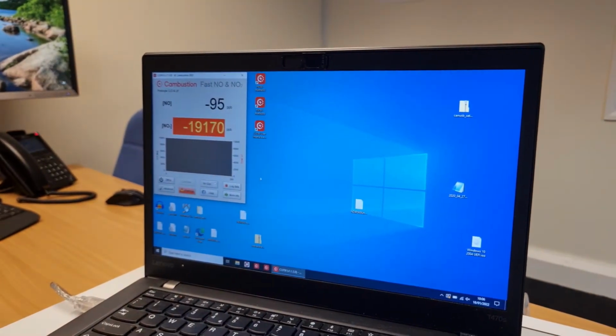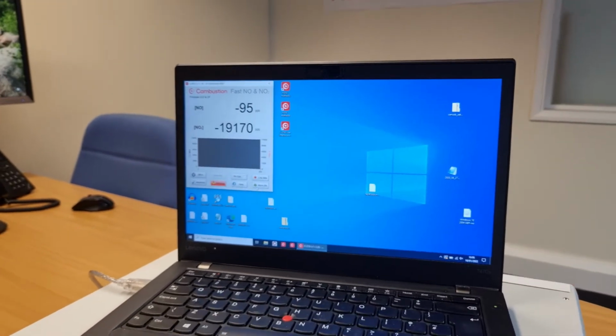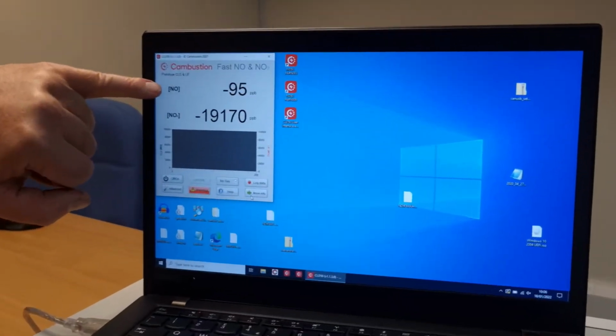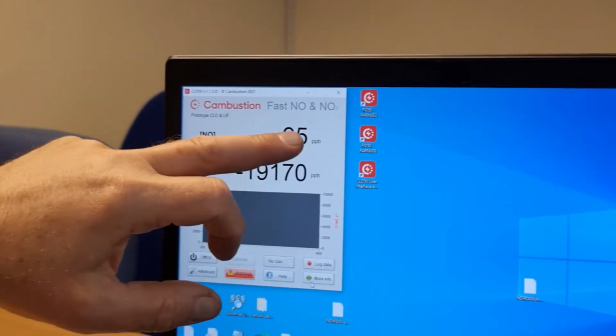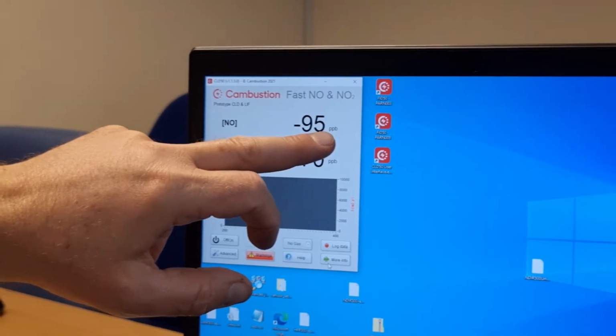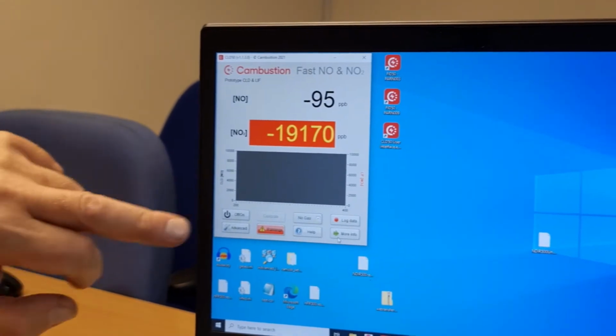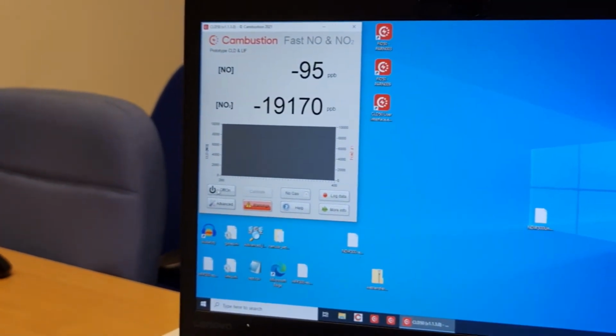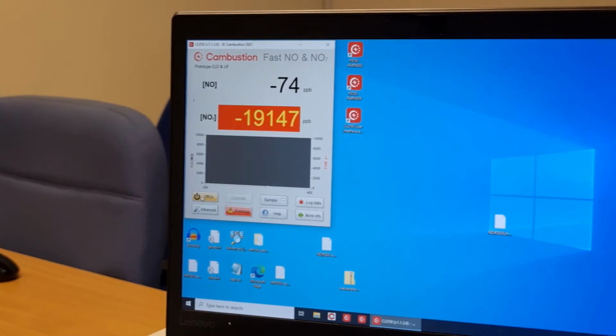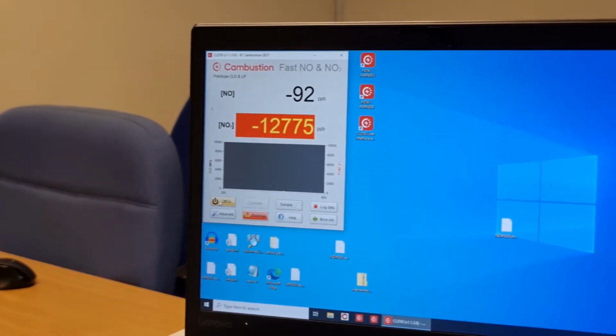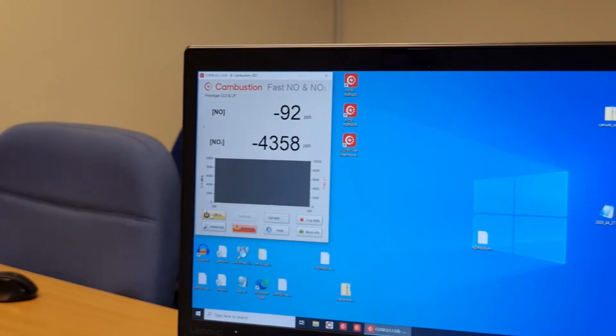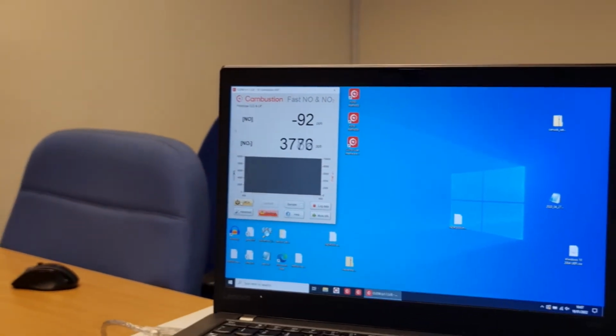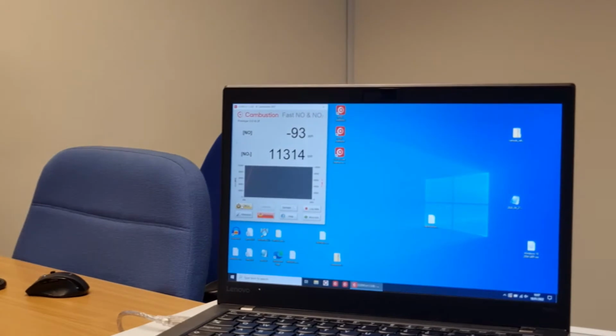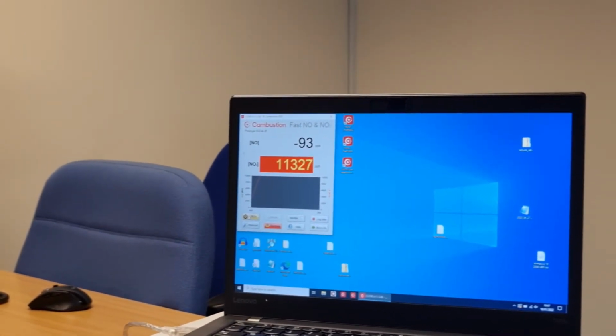But we have communications here now, and very broadly at the top we have an output. We haven't switched on yet, but we have our output, which is NO, and we can choose our parts per billion or parts per million ranges. Here is the output for the NO2. Here is our on-off button. So I'm now going to just switch on so that things start warming up. You can hear that pumps have started, and this will take approximately 30 minutes to warm up and reach a point where it can be calibrated.